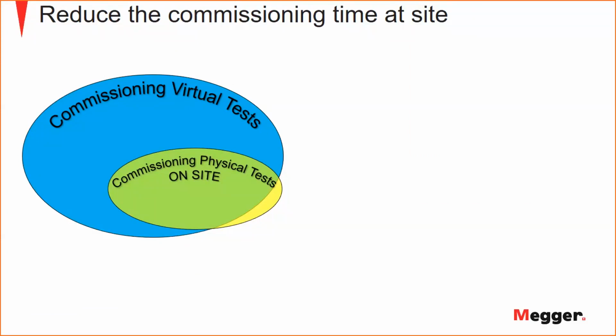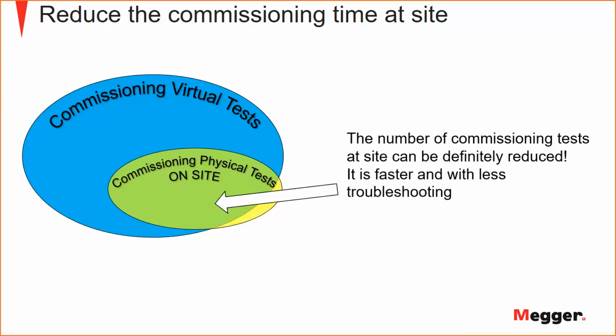And then if it's not, of course, you have to open the box. But if it behaves like it was behaving before, you have the confidence that your tests were okay, and that still the system has been mounted and connected and set and configured as it was supposed to be done. So you perform a subset of the testing on site.